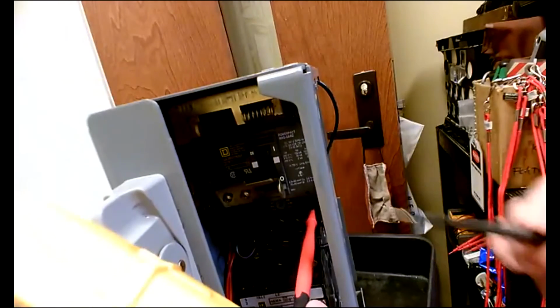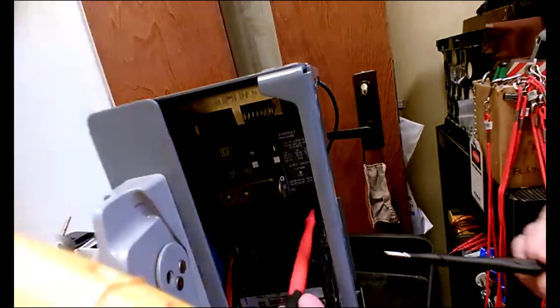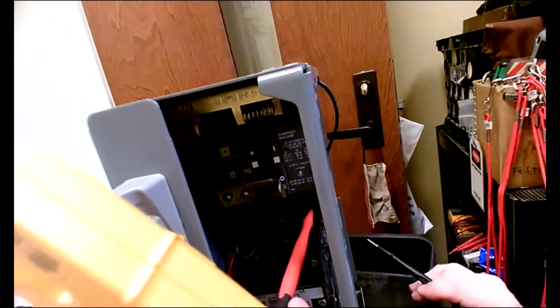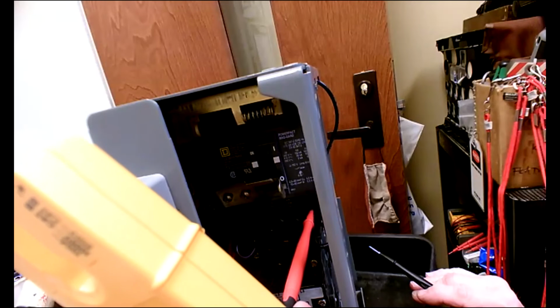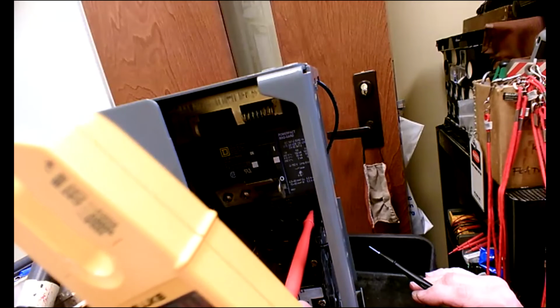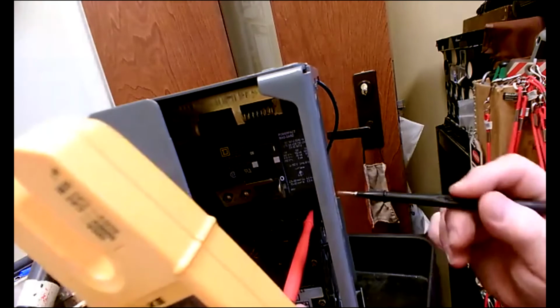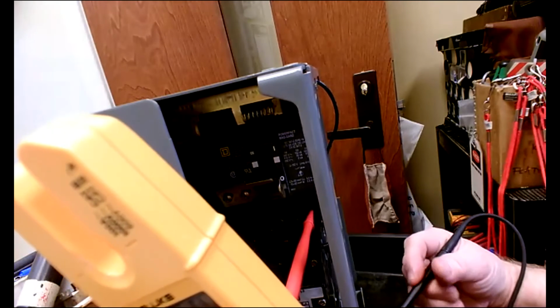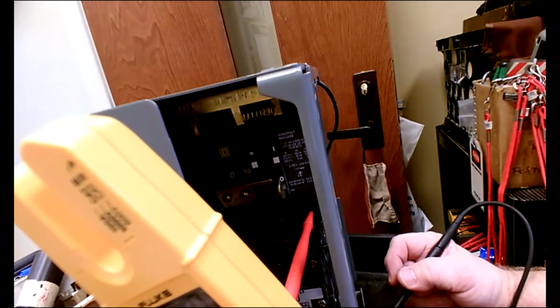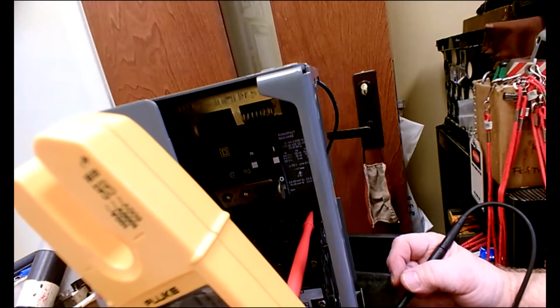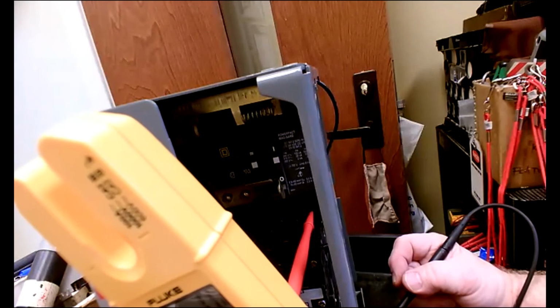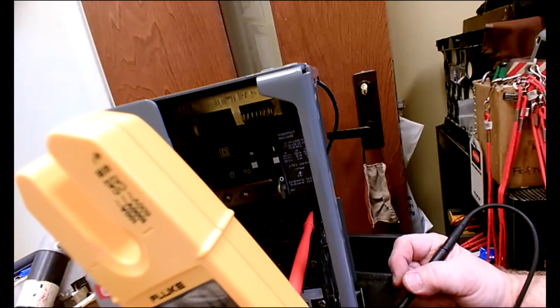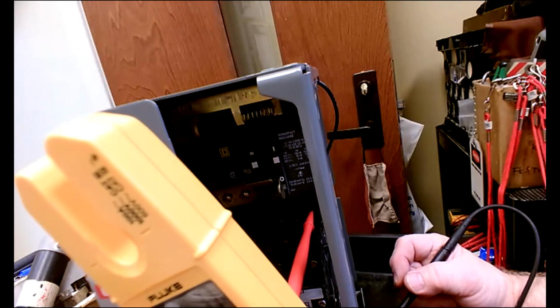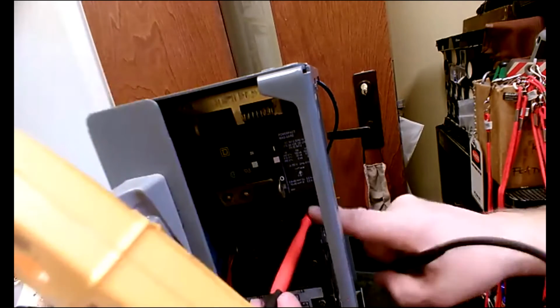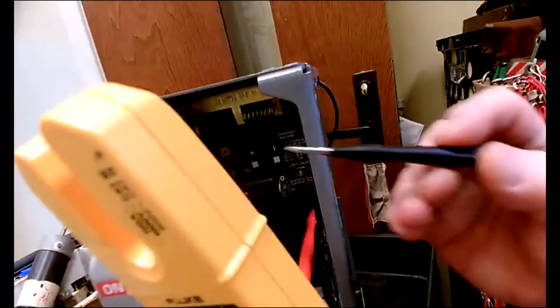And then I move to the third leg on the breaker inside there because it's three-phase power. This could be 240 three-phase, it could be 480 three-phase. I know they're telling you they want you to learn about three-phase. Now, three-phase, you're going to work with that in motor controls in January. Okay? We don't deal with three-phase in this class. You're going to stick with single phase. But starting in January, from January to May, you will deal with three-phase pretty regularly. But that third leg, we're going to check there, and we're going to go to ground.